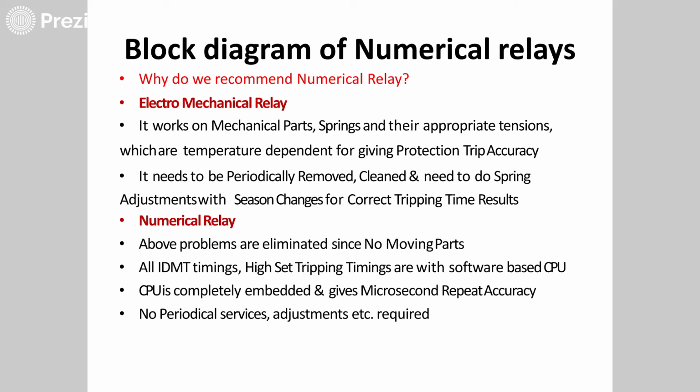Okay, so we are using numerical relays, right? But most of the relays, if you take your electromechanical relays, these kind of relays are not reliable, right? It is not reliable because it is going to use mechanical parts. It works in mechanical parts such as springs, and their appropriate tensions has to be maintained. The strain which is given on the springs has to be maintained. Okay, and then also it is temperature dependent for giving protection trip accuracy. That means depending upon the spring operation, your relay will be open or it will be closed, right?